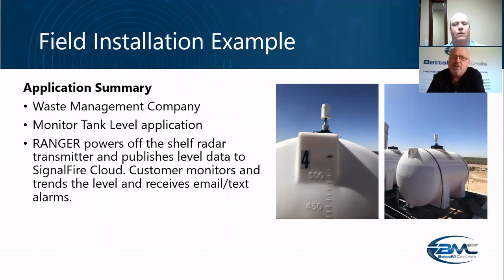So just to understand correctly, normally with SignalFire we have a gateway that speaks Modbus and has to talk to a cell modem or a T-box or something. But in this case, we just have the device, and all you have to do is map that into the broker, which could be a T-box or a third-party cloud-based broker. Then all we have to do is map into that broker as well on the other side, either from the SignalFire website or from VT SCADA via AutoSol.